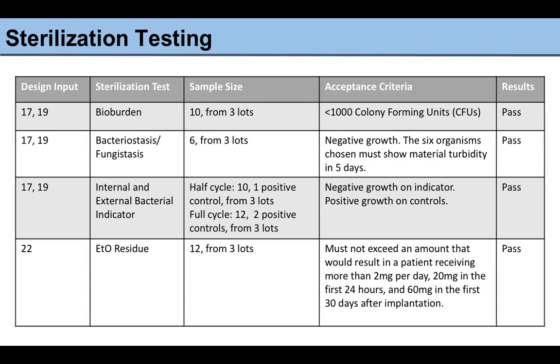We also had to confirm that the sterility of our device was not compromised and was not harmful to the patient. To do this, we first tested the bioburden of our device after sterilization, and all of the sample sizes for our sterilization testing are based on standards as well as risks associated with our design inputs. All of them also are required to be drawn from 3 separate production lots, so all of the numbers shown on this slide are the sample size each from all 3 lots. So the bioburden test has a sample size of 10 for a total of 30 from 3 different lots. And the acceptance criteria for this test is less than 1,000 colony-forming units, which passed.